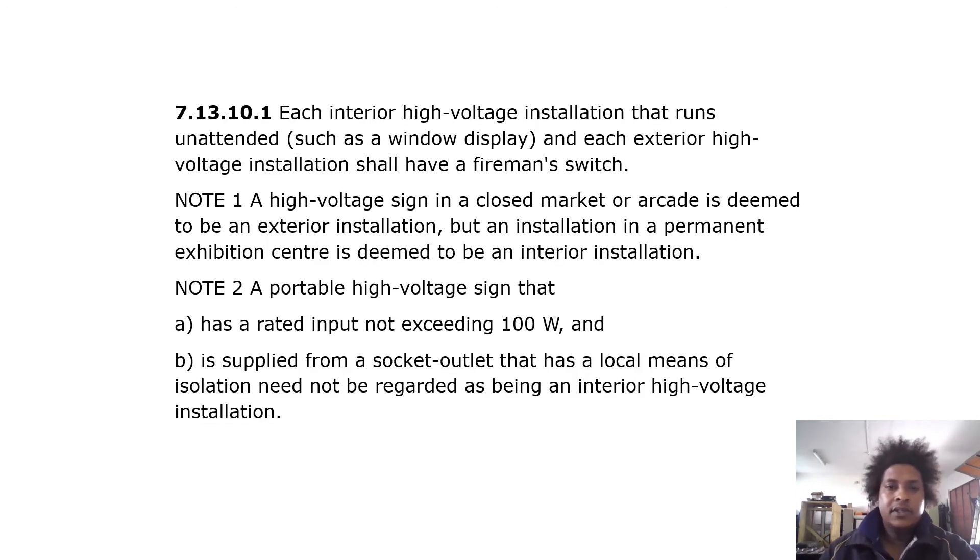Fireman switch: each interior high voltage installation that runs unattended, such as a window display, and each exterior high voltage installation shall have a fireman switch. Note 1: a high voltage sign in a closed market or arcade is deemed to be an exterior installation, but an installation in a permanent exhibition center is deemed to be an interior installation. Note 2: a portable high voltage sign with a rated input not exceeding 100 watts supplied from a socket outlet with a local means of isolation need not be regarded as an interior high voltage installation.